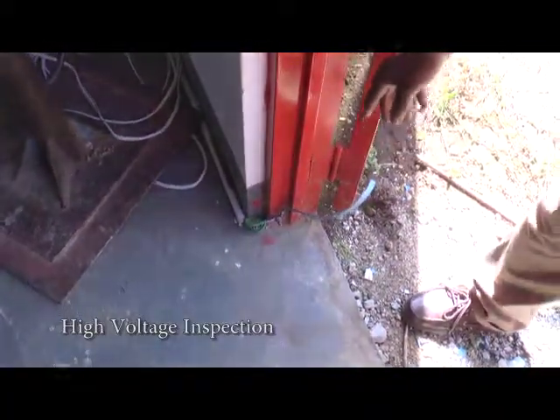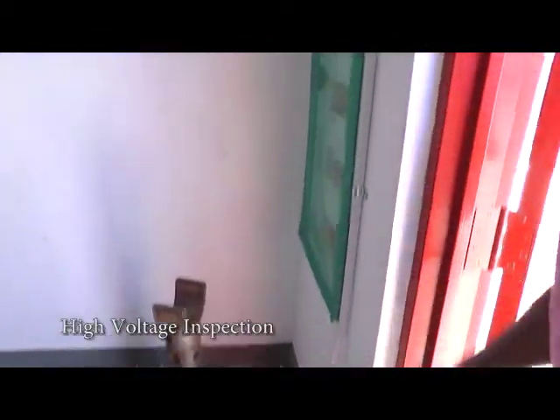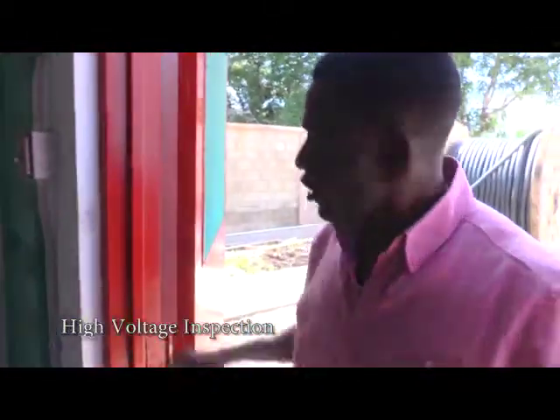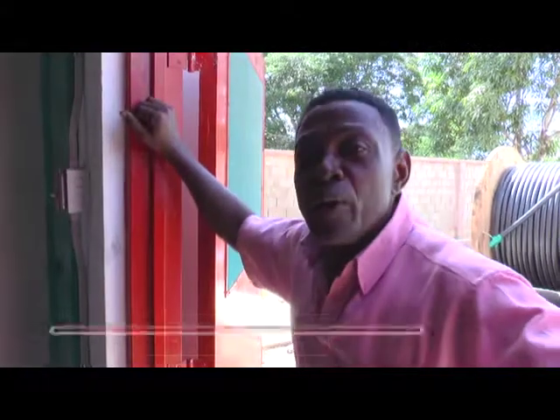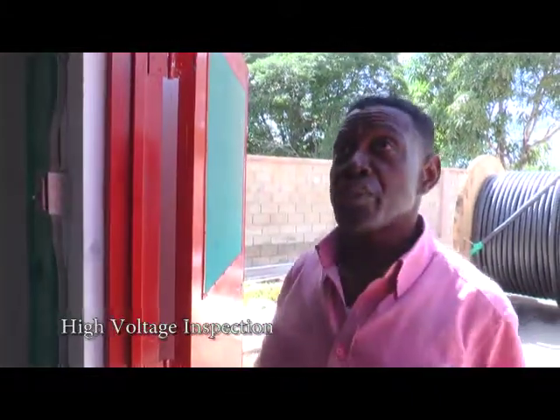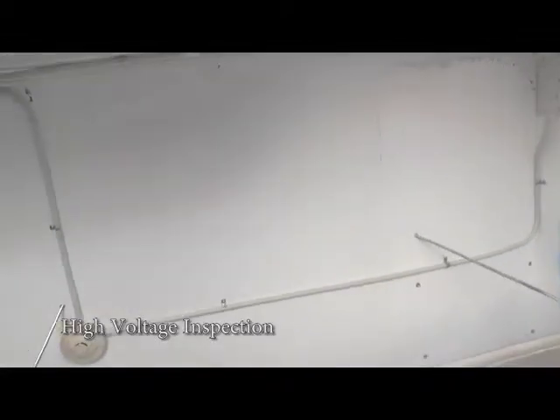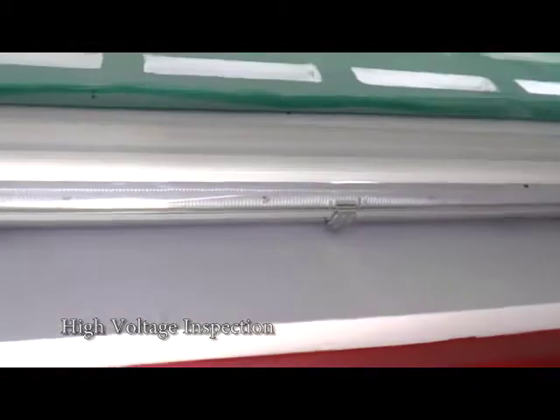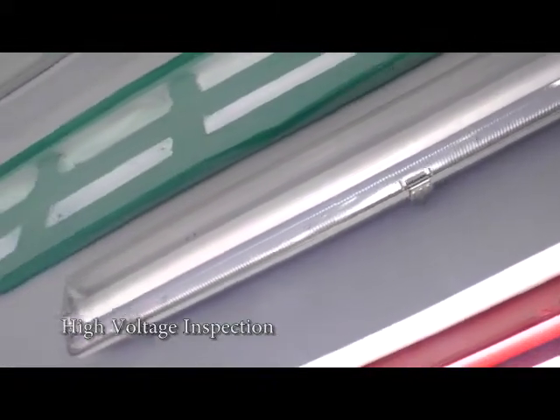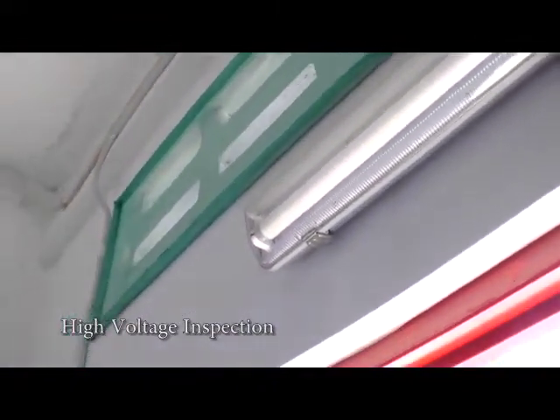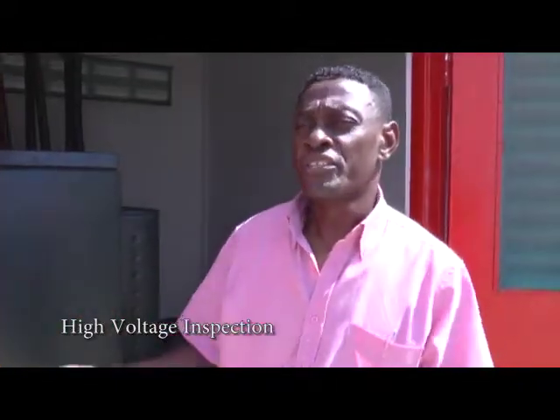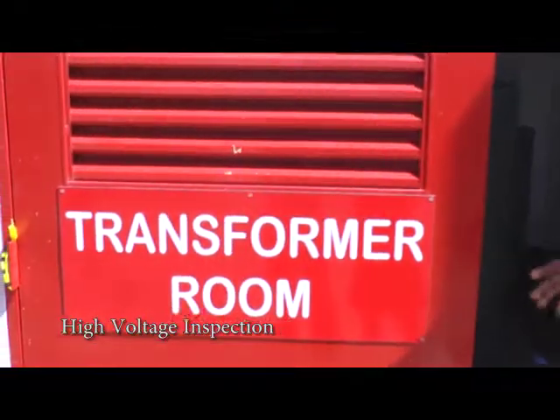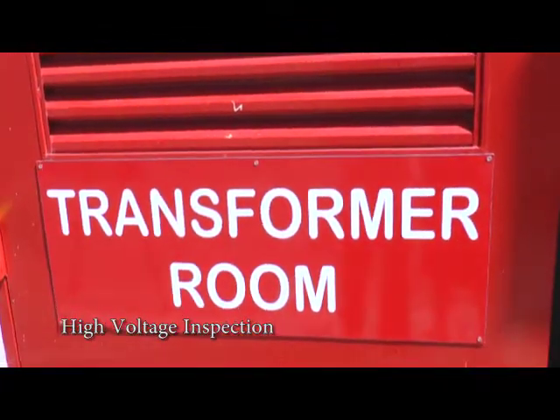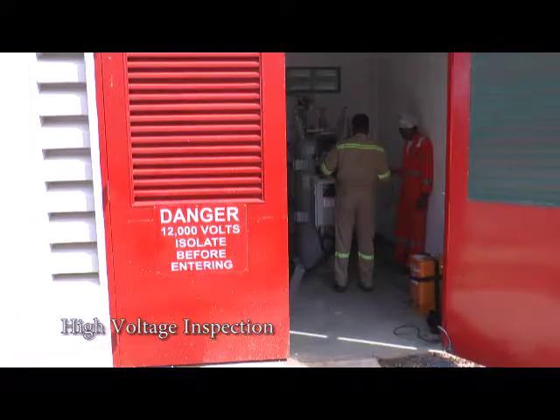Metal hooks must be earthed. Go back to the general master of earthing. This is to ensure that non-current-carrying metalwork must be at zero potential within the transformer room. We are also to ensure the structure is properly done. There is concern with regards to leakage of water within the transformer. Lighting must be efficient, the level of illumination must be good enough to have the work done in an efficient fashion. So that all the signs are placed on the transformer room, switchgear room, and other low voltage rooms to indicate that there is danger.